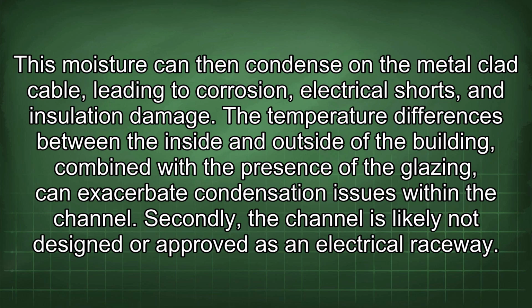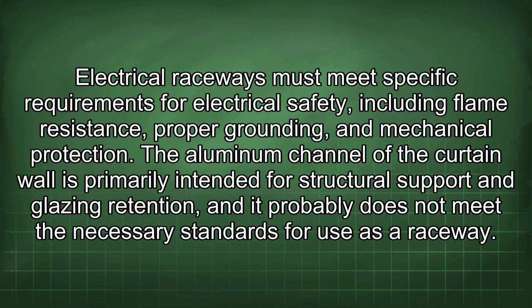Secondly, the channel is likely not designed or approved as an electrical raceway. Electrical raceways must meet specific requirements for electrical safety, including flame resistance, proper grounding, and mechanical protection. The aluminum channel of the curtain wall is primarily intended for structural support and glazing retention, and it probably does not meet the necessary standards for use as a raceway.